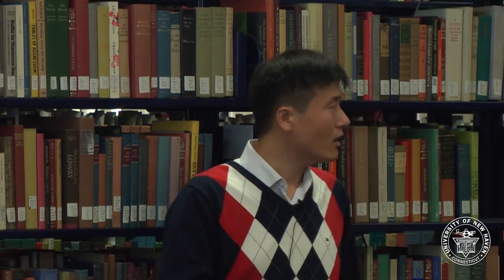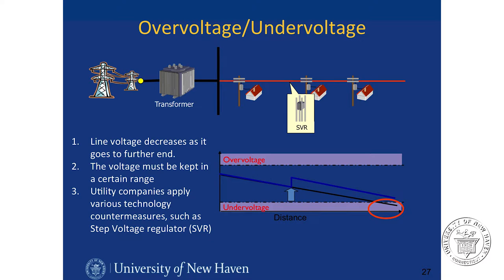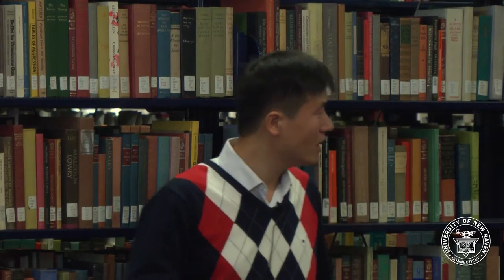Just like running water, voltage is the same. Usually in the distribution network, current flows from high voltage to low voltage, and along the transmission line, we have voltage drops. If the distribution line is too long, at the remote end the voltage may drop out of the security range, because we have a range of operating voltage. The voltage must satisfy or stay within this range, otherwise it will cause security issues. If there are voltage issues, we need to use devices such as step voltage regulators to boost up the voltage so that the overall voltage can stay within the security range.